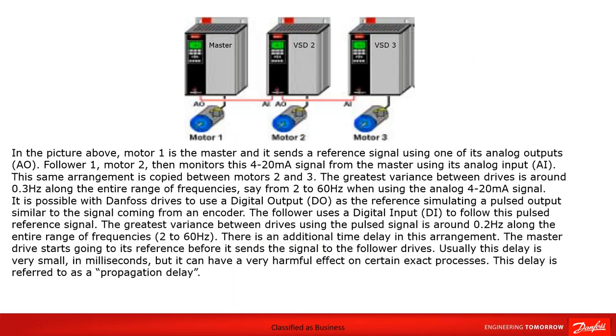So here, what we're showing is the motor, motor one, and the master drive. What that does, it sends a reference signal using one of its analog outputs, which I've already mentioned, to the follower one, which is motor two, and then monitors the signal, which is the 4 to 20 milliamp signal from the master. It uses its analog input, and this same arrangement is then copied between the second and third motors, as we're showing here. And the greatest variance between drives is usually around 0.3 hertz along the entire range of frequencies, so say from 2 to 60 hertz, when using that 4 to 20 milliamp analog signal.